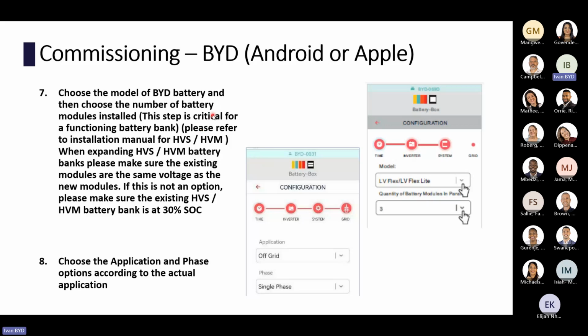Another step which I feel I should mention here is when expanding on high voltage batteries. Because the batteries are in series, it's always a good idea to have the batteries at the same SoC when expanding. When batteries are low voltage batteries, they're all in parallel. So if you put a 100% SoC battery with a 50% SoC battery, the 100% SoC battery can discharge into the 50% SoC battery to equalize the voltage and the SoC. Whereas if you're in series, which the high voltage batteries are, there's not that possibility. So it's always a good idea to make sure the voltage of your modules is all the same when you expand. And if you don't necessarily have the ability to do that, it's best to make sure that your existing bank is at 30% SoC, because the batteries almost always ship at 30% SoC.